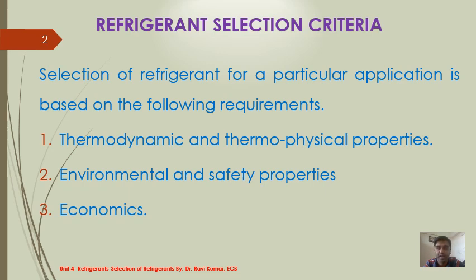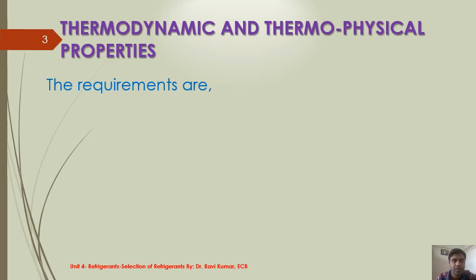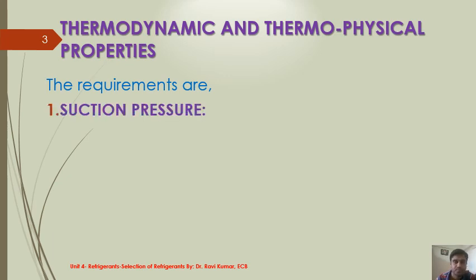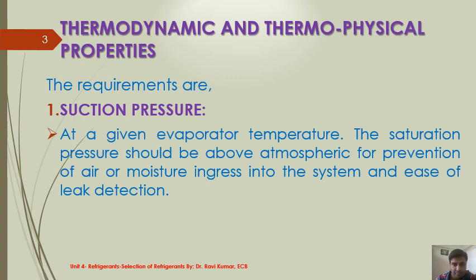We go to the first: thermodynamic and thermophysical properties. The first property requirement is suction pressure. At a given evaporator temperature, the saturation pressure should be above atmospheric for prevention of air or moisture ingress. This means the refrigerant selected should have a positive pressure, i.e., the evaporator pressure should be above atmospheric.